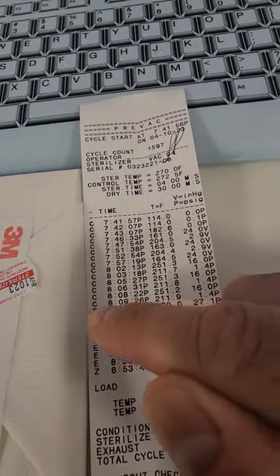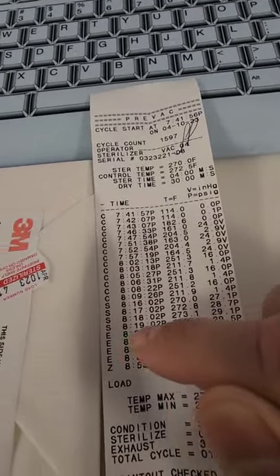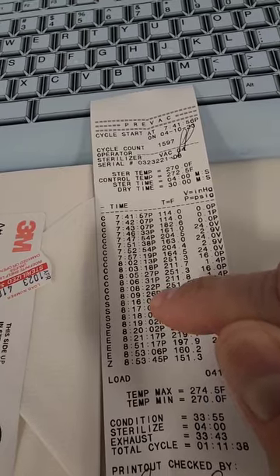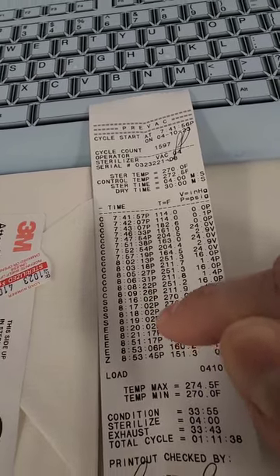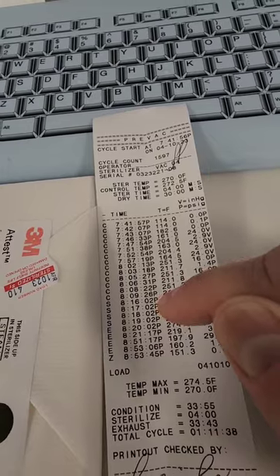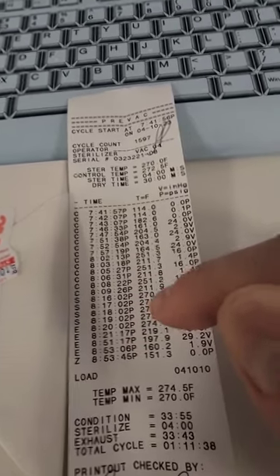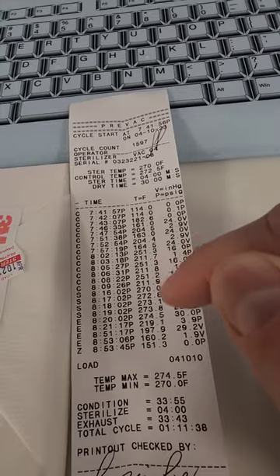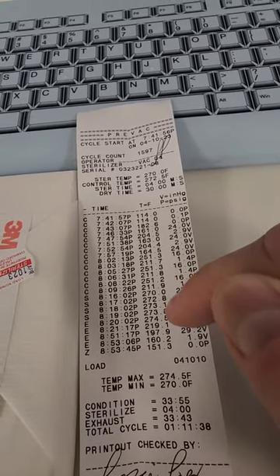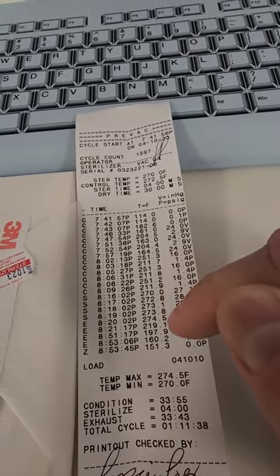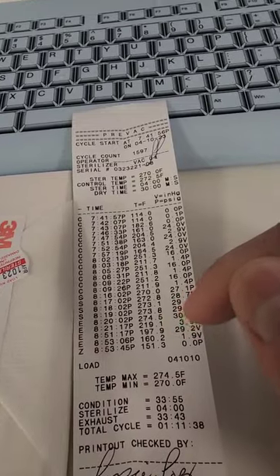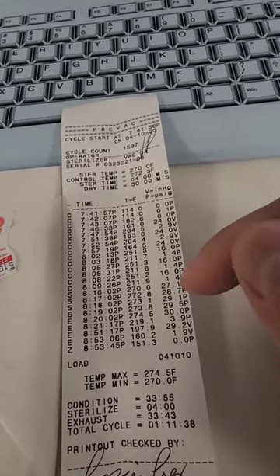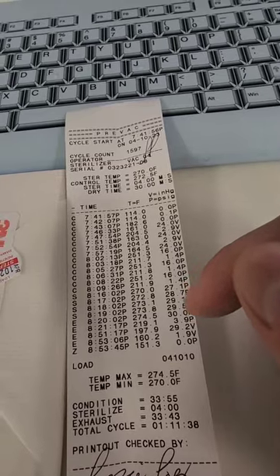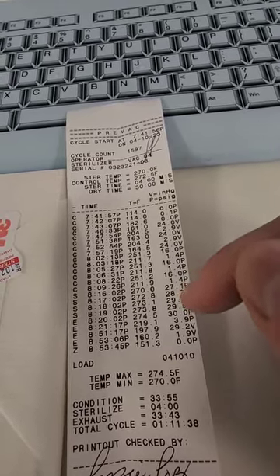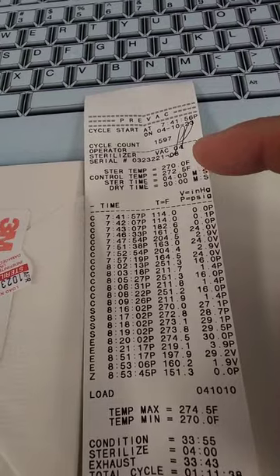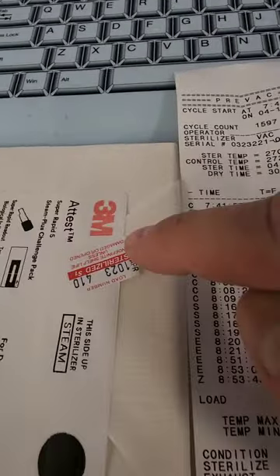That first initial there is the initial of the individual who started it, which was me, and the individual who checks it, full signature at the bottom, which is me as well. So what am I looking for? I am looking for the confirmation of the parameters I checked. I want to look at the time, the temperature, and the pressure, because I set this machine for a 270 degree, 4 minute exposure, 30 minute dry time cycle. All of that is outlined there, and I want to confirm it.